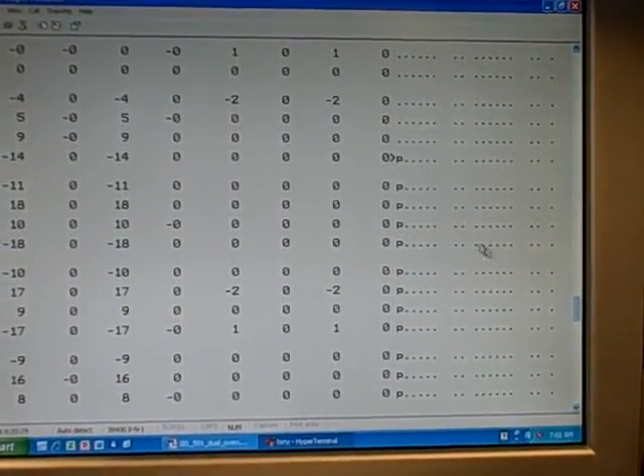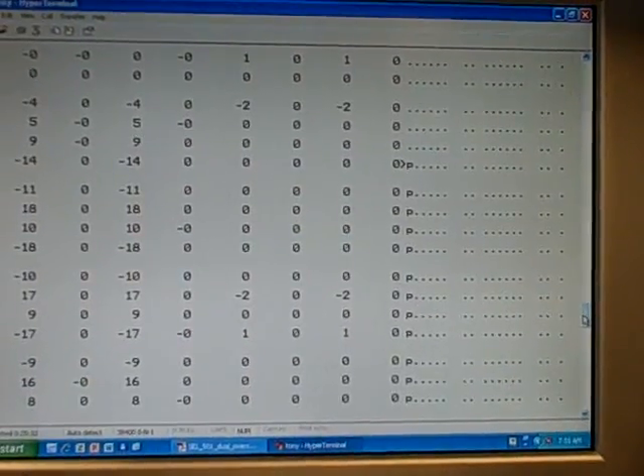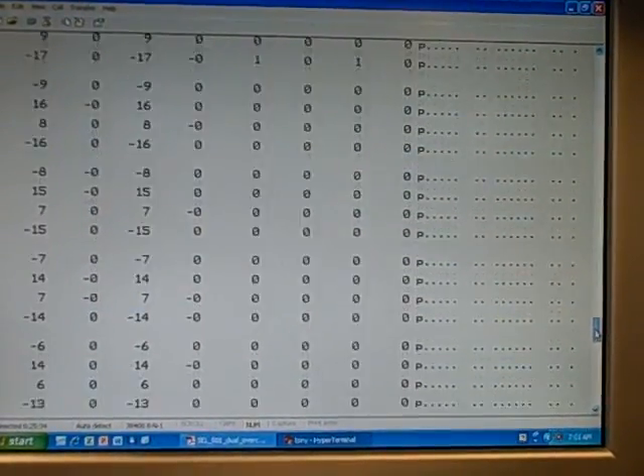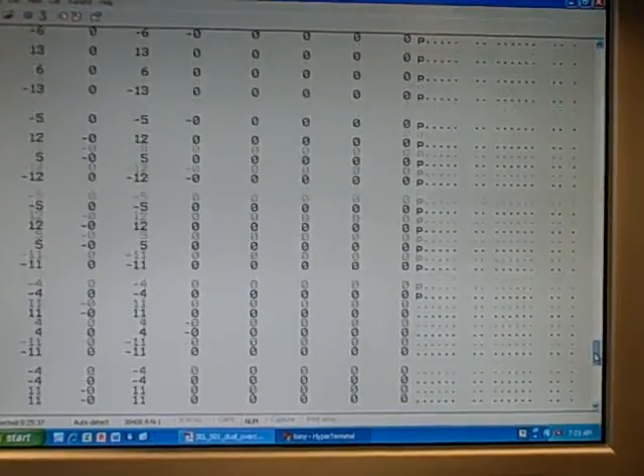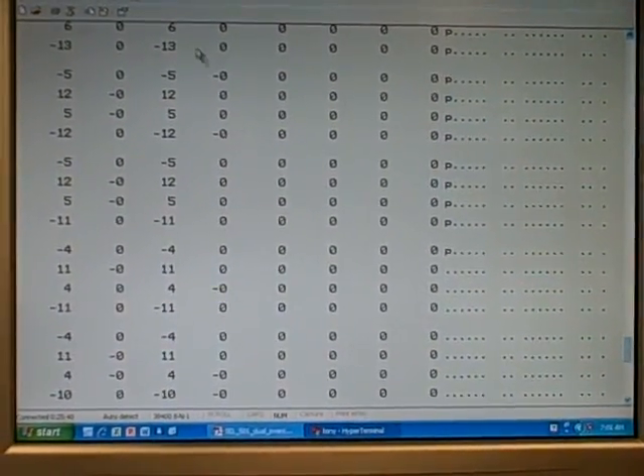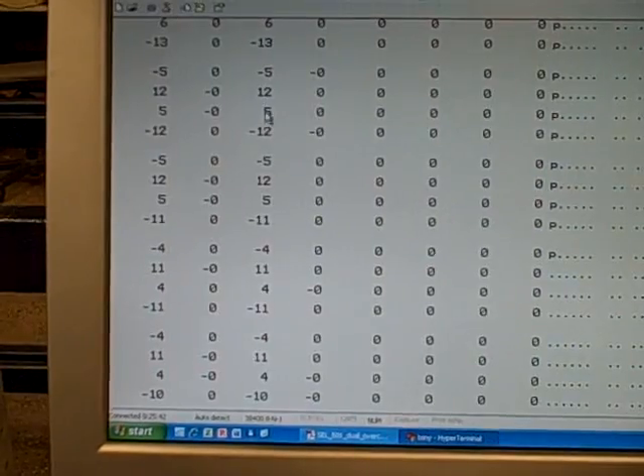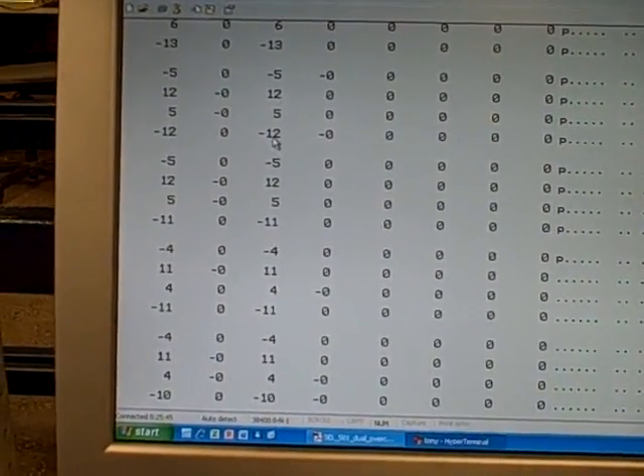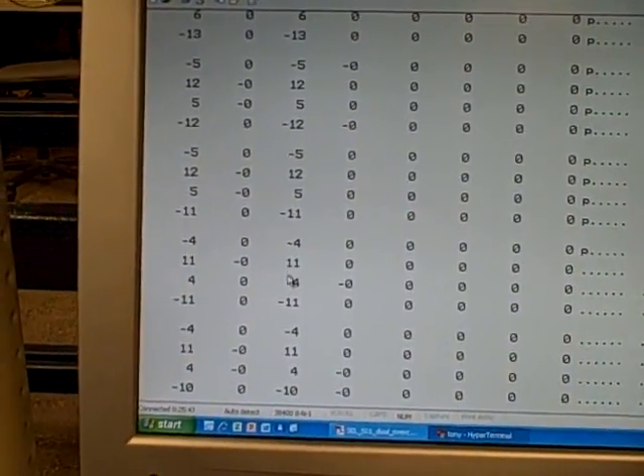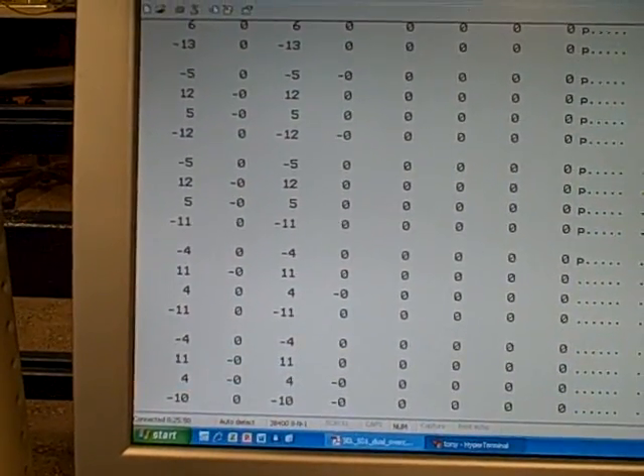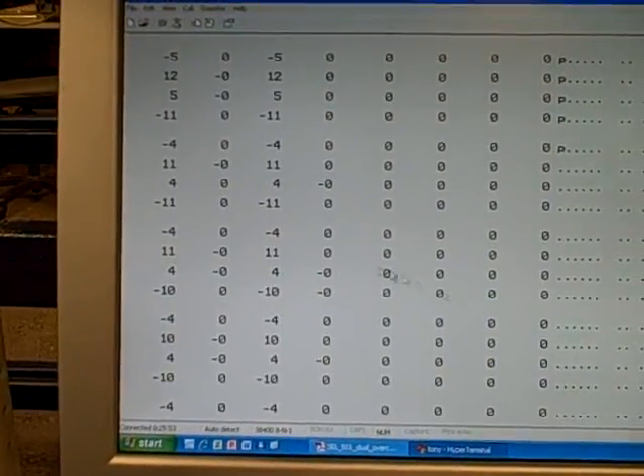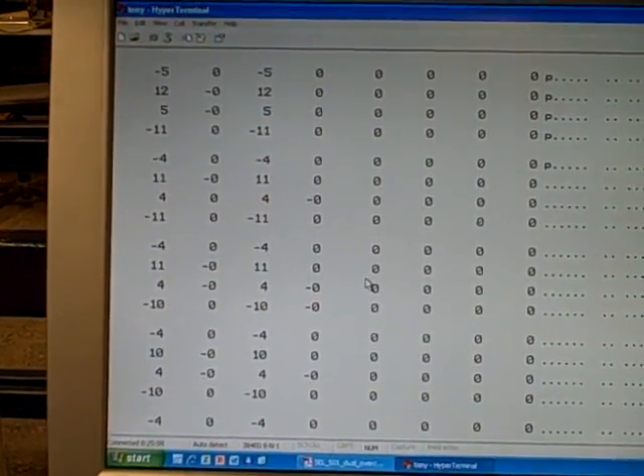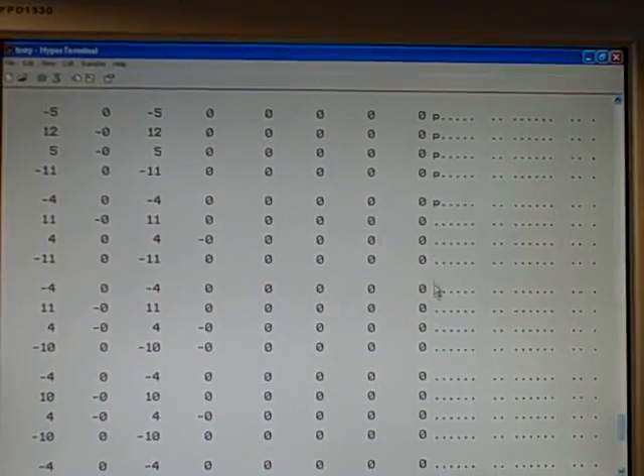Now moving down, we see the letter P persisting for a few more cycles, then finally it goes away. And you can see why. If you trace these values in the current column, you see basically hitting a peak of about 12 amps here, a peak of 11 amps, a peak of 10 amps. As the motor's inrush current falls off, eventually we fall below the pickup value for the time over current element, and that's when the letter P disappears.